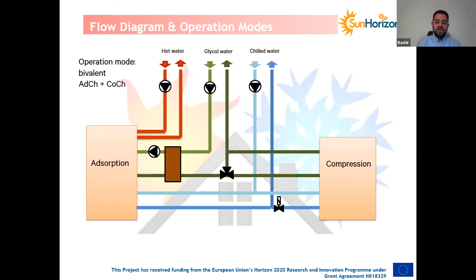Within the scope of Sun Horizon, we are installing a hybrid chiller in the demo site in Satkugat. It has a capacity of up to 100 kilowatts. From that, the adsorption part covers up to 40 kilowatts, and the compression part covers up to 60 kilowatts. We are using propane as a refrigerant in the compression part, and as I said, of course, water in the adsorption part. And yes, we are using solar energy, of course, as a drive energy for this demo site.